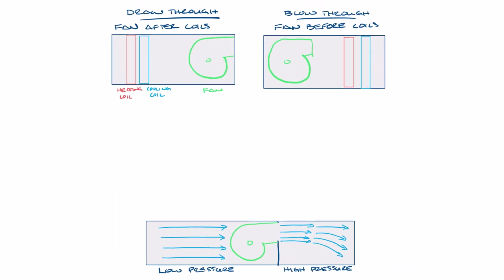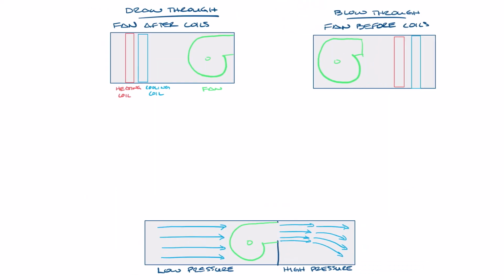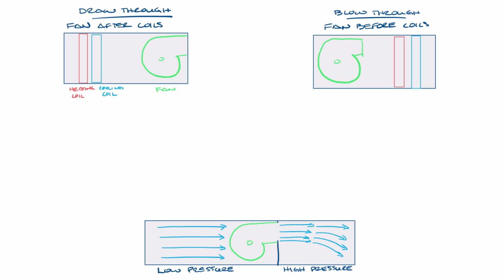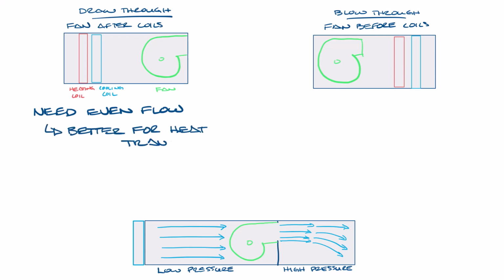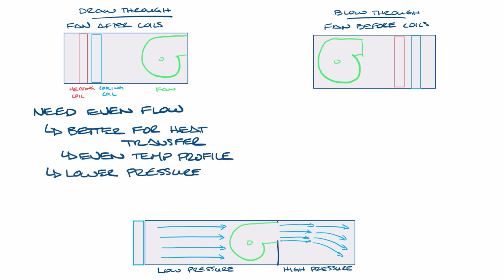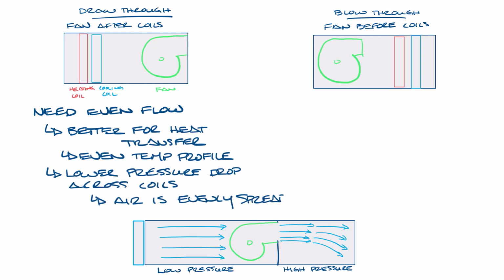Let's bring the top back on now and move these over a little bit to make some room for me to write. So when you look at how the air is moving, if you need a more even flow, you want to use a draw-through configuration. So if there's a water coil over here, air is being pulled evenly over the coil. This is better for heat transfer from the coil to the airstream, and you get a fairly even temperature profile. You also have a lower pressure drop across the coils if the air velocity is evenly spread across the coil face.